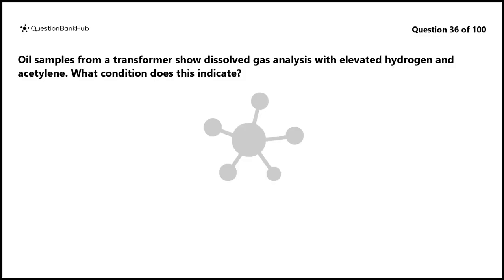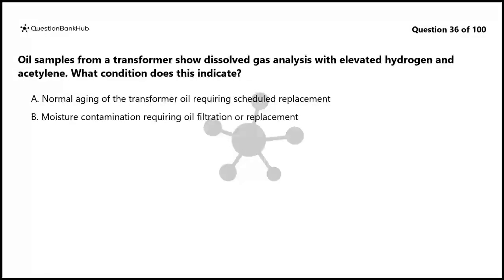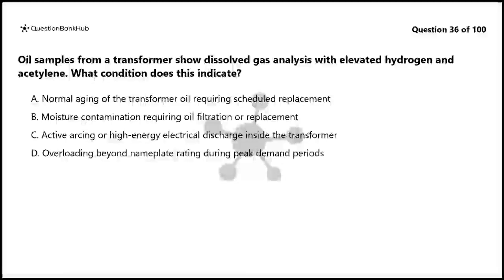Question 36. Oil samples from a transformer show dissolved gas analysis with elevated hydrogen and acetylene. What condition does this indicate? A. Normal aging of the transformer oil requiring scheduled replacement. B. Moisture contamination requiring oil filtration or replacement. C. Active arcing or high-energy electrical discharge inside the transformer. D. Overloading beyond nameplate rating during peak demand periods.